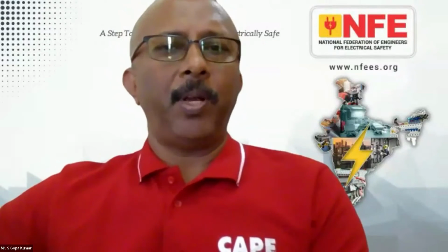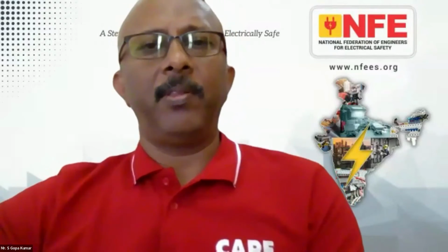Why, sir, and where is this installed? Mr. Ronak Desai - okay Mr. Ronak, hope the question is clear to you, you have to unmute. Yeah, so SVC is of course one of the compensation methods, especially for steel plants and arc furnaces. It takes care mostly of voltage control and power factor compensation, but yes, the harmonics component can also be taken care of through SVC design. Only thing is that the design, as explained by Ravi sir, the design aspects of SVC have to be handled with proper measurement of the harmonics components generated from the end equipment.